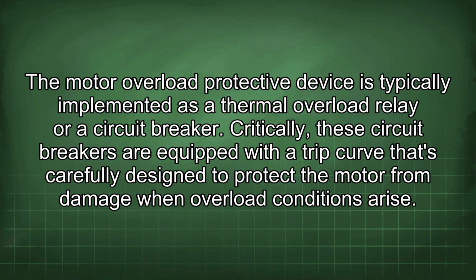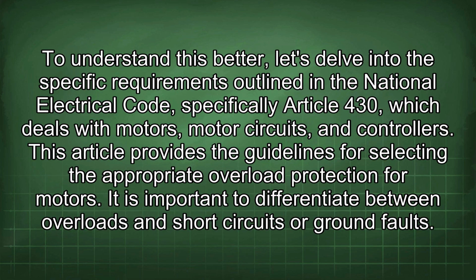Critically, these circuit breakers are equipped with a trip curve that's carefully designed to protect the motor from damage when overload conditions arise. To understand this better, let's delve into the specific requirements outlined in the National Electrical Code, specifically Article 430, which deals with motors, motor circuits, and controllers. This article provides the guidelines for selecting the appropriate overload protection for motors.